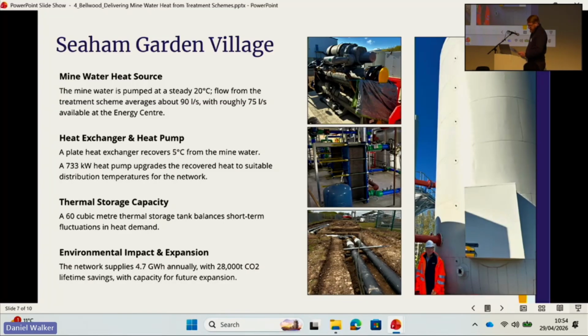Inside the energy centre, around 5 degrees of heat is recovered using a plate heat exchanger before the mine water continues off into the treatment process. The site has a 733 kilowatt heat pump, which lifts the recovered heat up to the temperature needed for the network. There's also a 60 cubic metre thermal storage tank, which helps smooth out any short-term swings in heat demand.